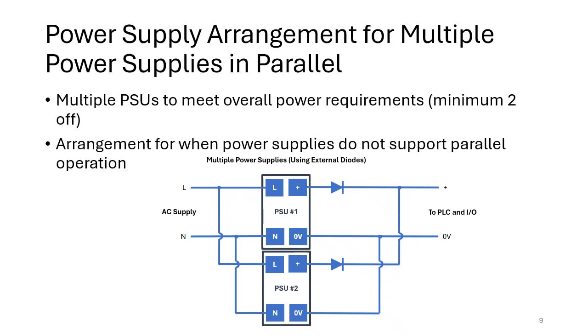So for example, if you consider the PLC output, which might also have a diode inside, you might have resistance at the terminations which reduces the voltage. So you might start with 24 volts at the power supply, but you might be down to 20 volts or even lower at the actual physical output, and that might not be enough voltage or power to actually control the output.